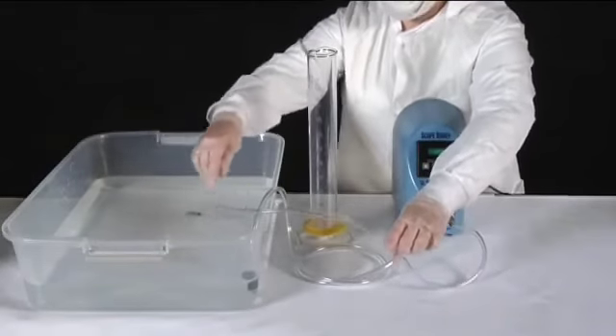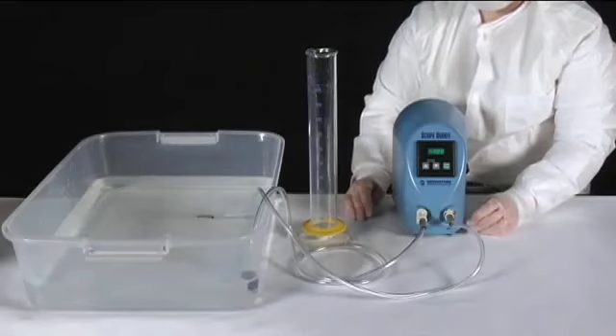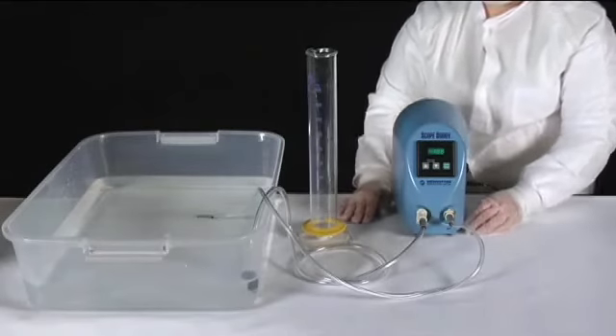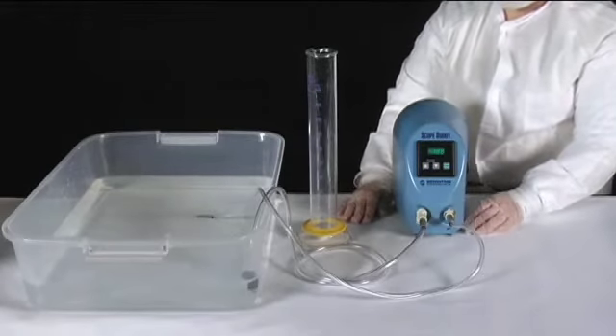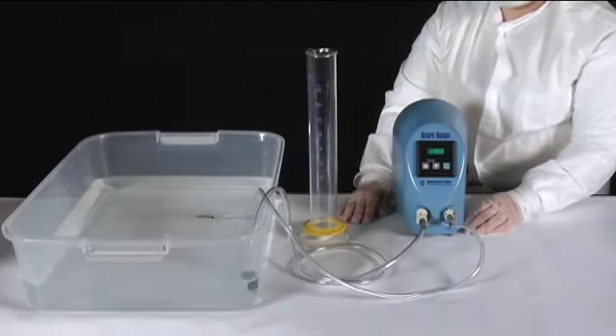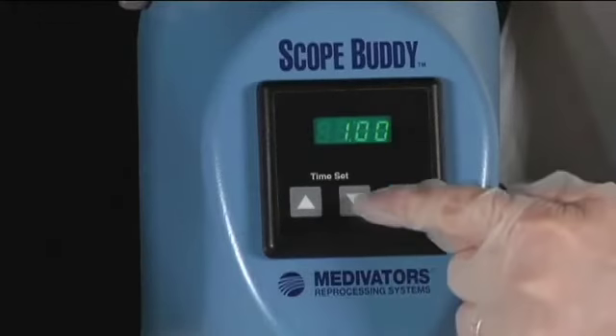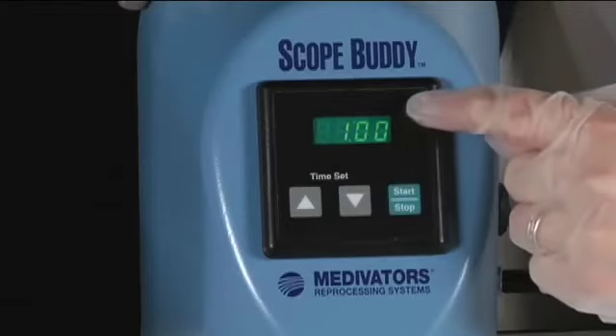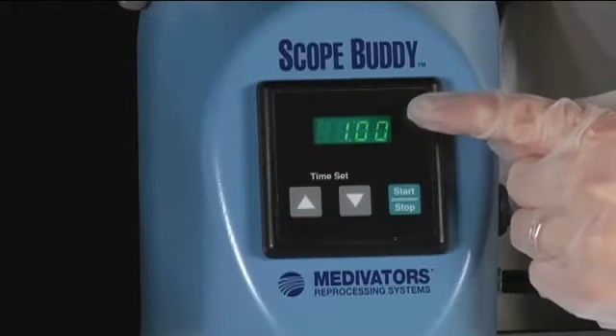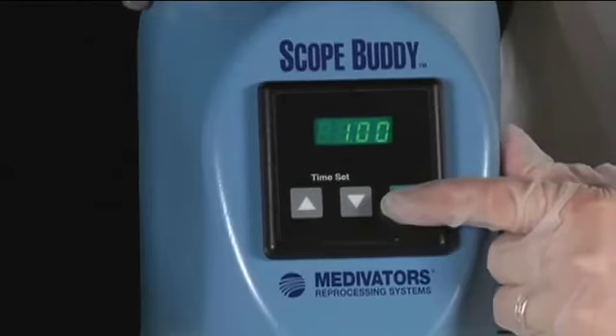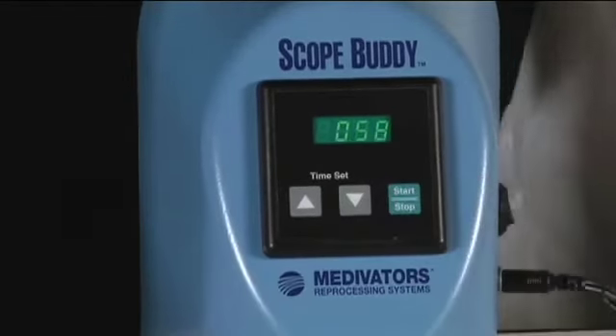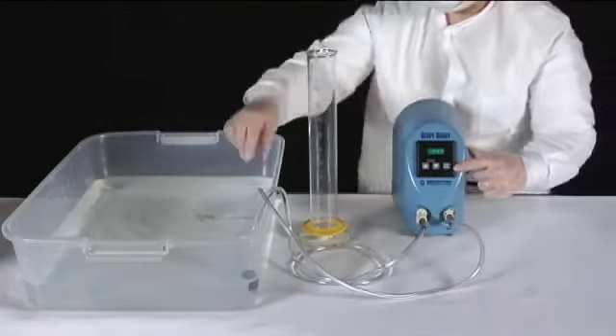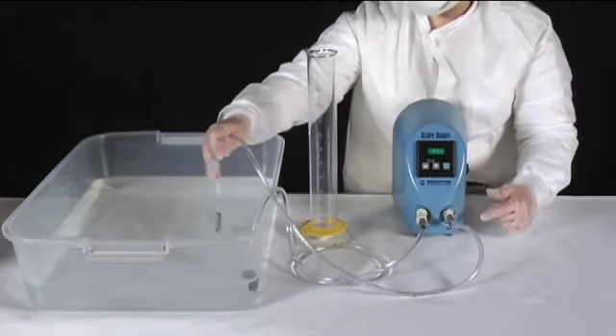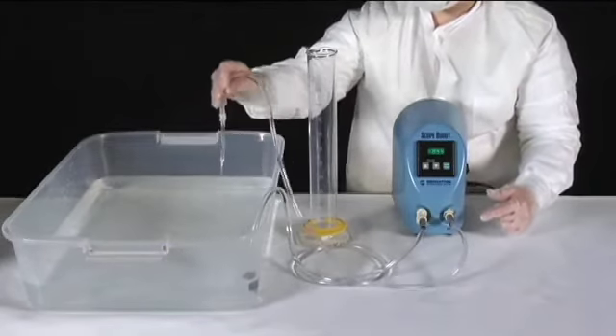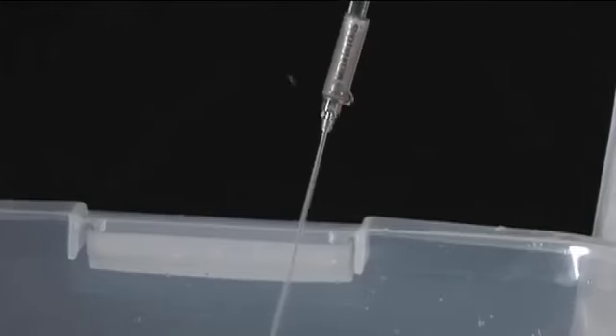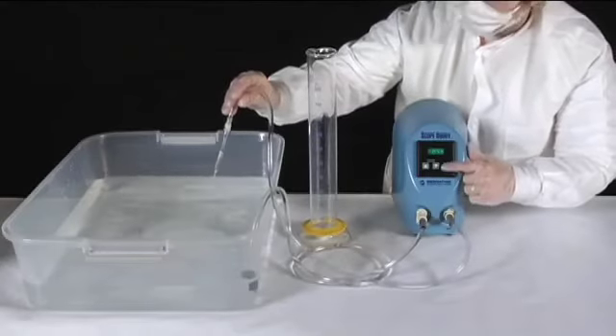In order to perform the daily quality assurance test, the tubing will need to be primed with water. Priming can be accomplished by using the Scope Buddy front panel arrow keys, set the time until it displays 1 minute. Press the Start-Stop button to begin delivering fluid. Watch until all air has been purged through the device and a steady column of water is exiting the flow verification tube. Press Start-Stop button to halt flow.